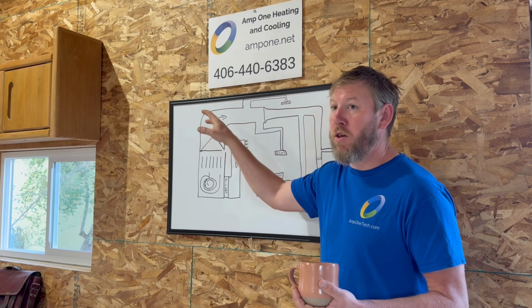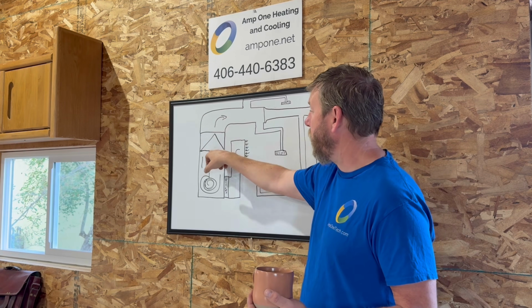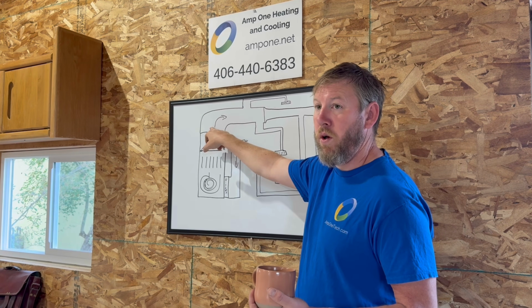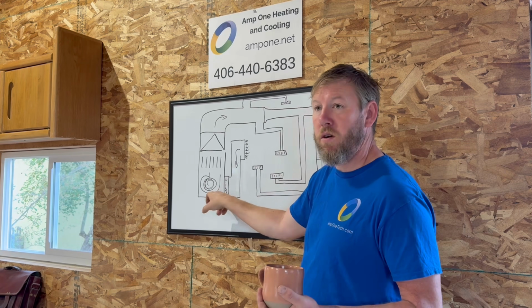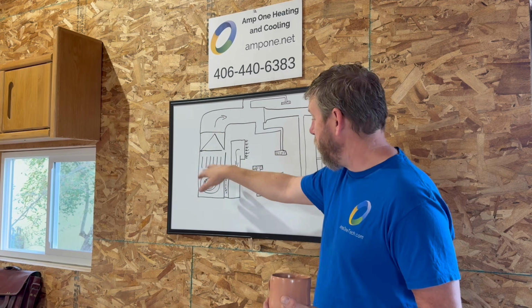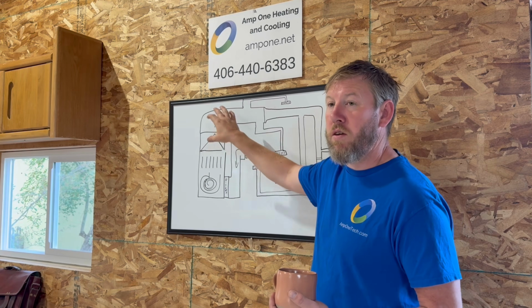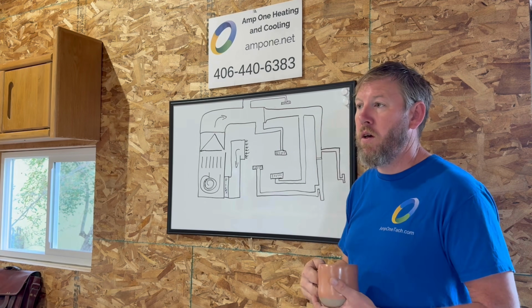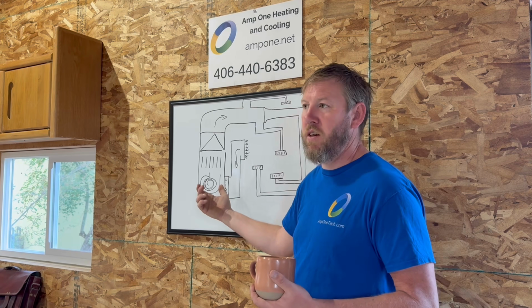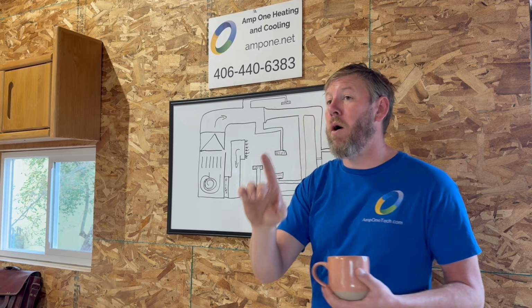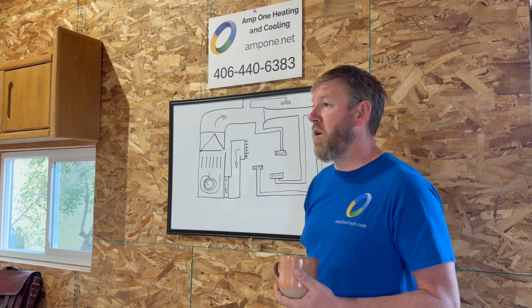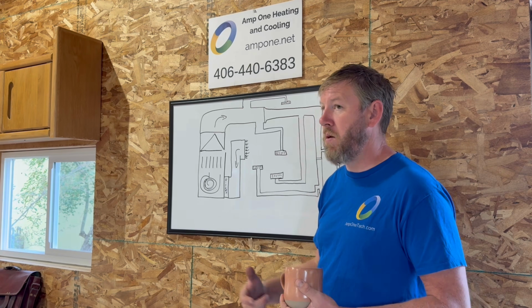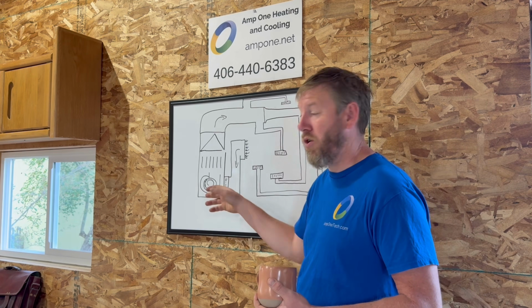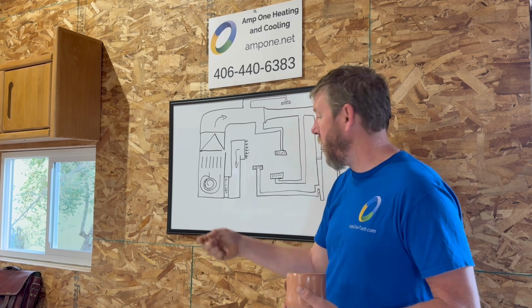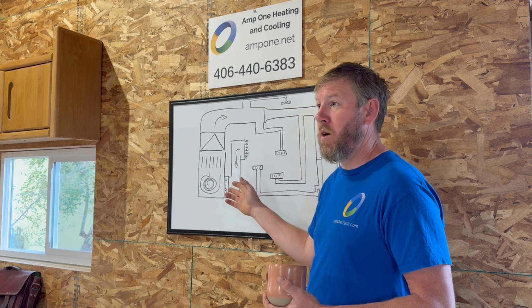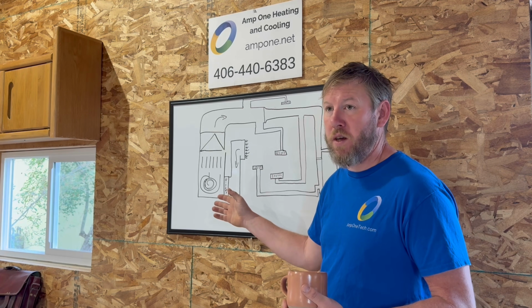the furnace. Now you can also check your static pressure across your coil, across your filter, and basically what you're doing is just looking at what each thing is doing and how much drop is across it. It's easy just to pull out a filter and check to make sure it's good. But what you don't know is the filters that they're using might be too high of a MERV rating. It's trying to pull too much out. Happens all the time. They're set up for an 8 MERV. They go to Costco and they buy a 14.